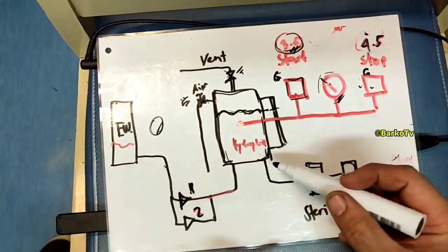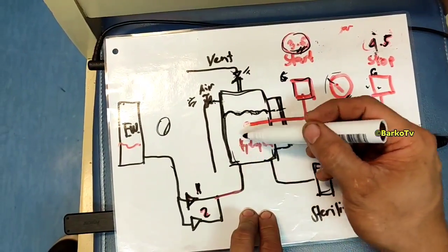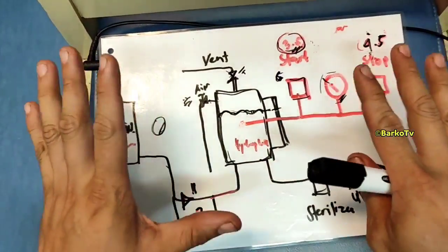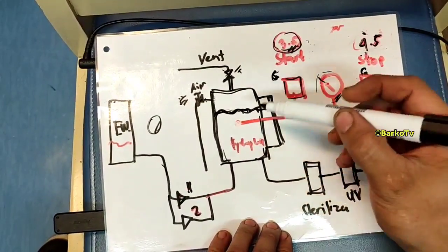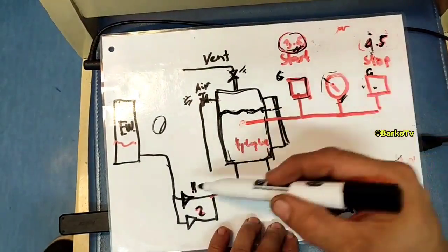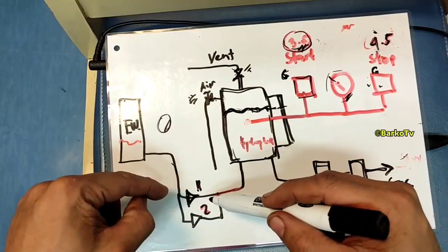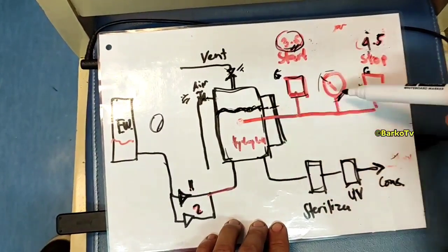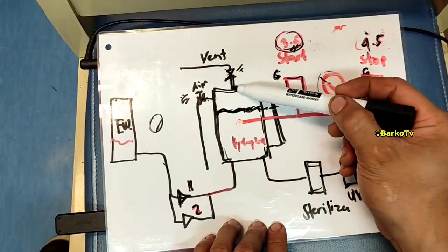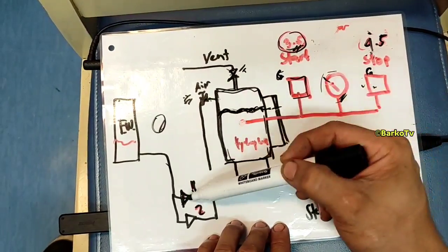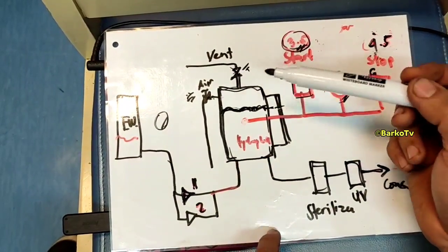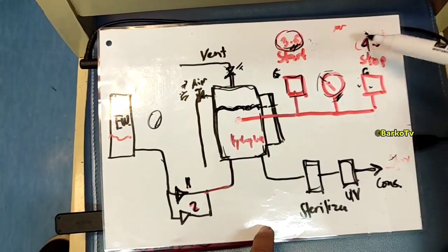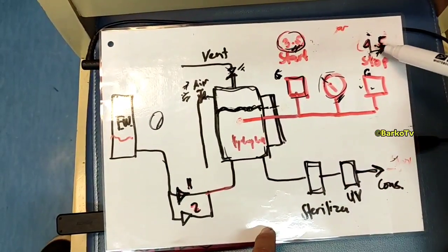First, you need to fill up the hydrophore. Press start — run in auto or manual — and fill it up. Fill to three-quarters with water, without pressure, then vent it down. After filling up, stop the pump and then charge air manually.